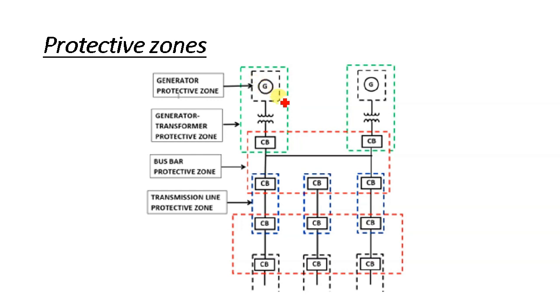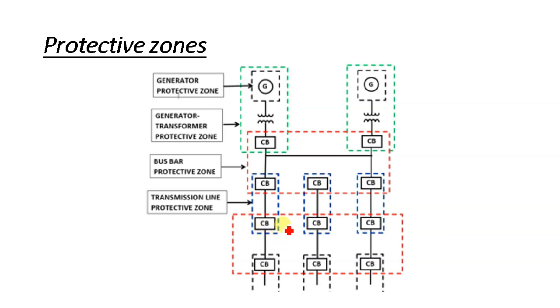This is the basic diagram of a protection zone. Here you can see we have a generator, a step-up transformer, then a bus bar, and then a transmission line. You can see the circuit breakers. This is known as the generator protective zone. The second is the generator-transformer protective zone, shown by the green dotted line. The third is the bus bar protective zone, and the transmission line protective zone is shown in the blue line. Three parallel transmission lines are going out, and you can see circuit breakers at each end along with the protective zones.